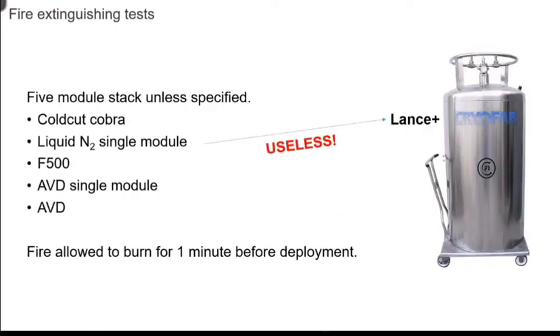Liquid nitrogen was useless. F500 killed the fire within 7 seconds, and it stopped thermal propagation to the top 3 modules. But whether that's due to the surfactant plus water mist or just to the water mist, we're about to do new tests to try and investigate.